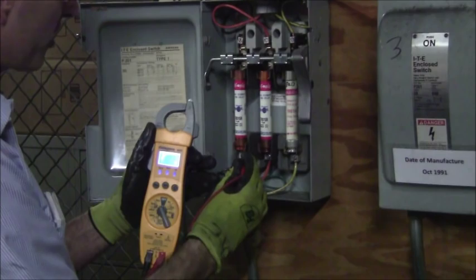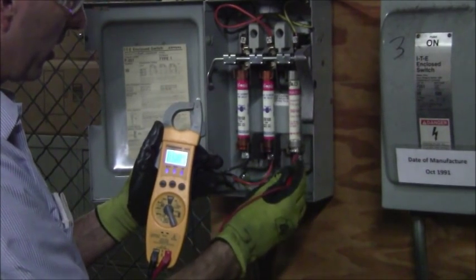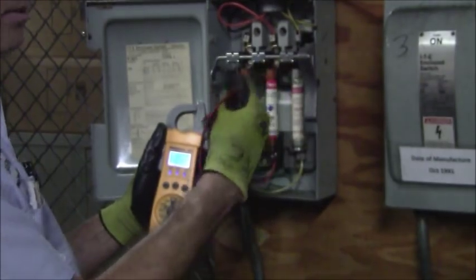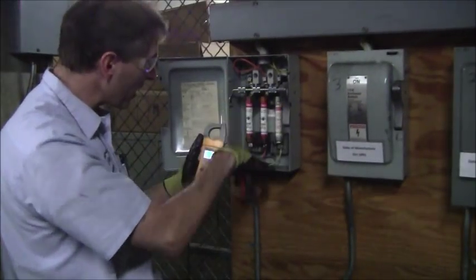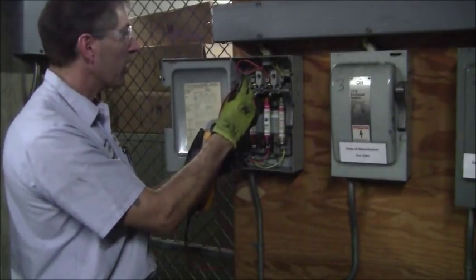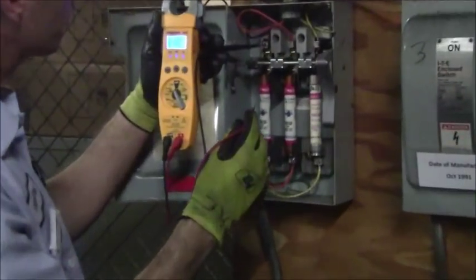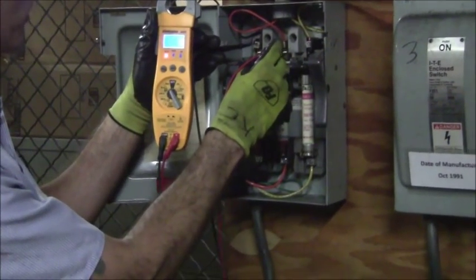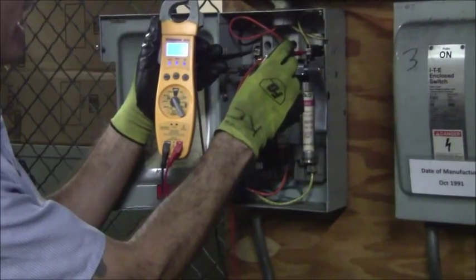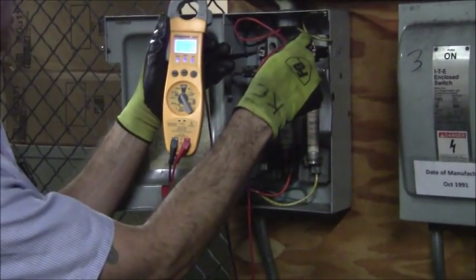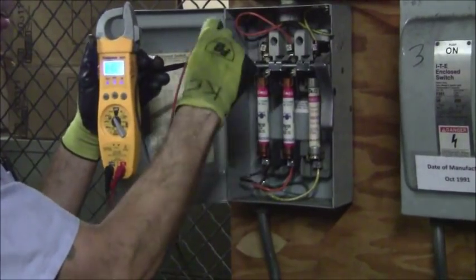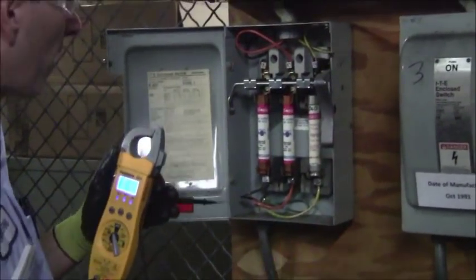Now I'm just going to come down here and check it like this. Nothing. Now I'm going to just check the tops. Nothing. So the fuses and everything downstream is safe. I'm live at this point. I'm going to go ahead and do phase to phase over here at the hot point. Got 486 volts on A to B, and this is A to C, 489. So we're completely good on all 3 phases, giving us 480.